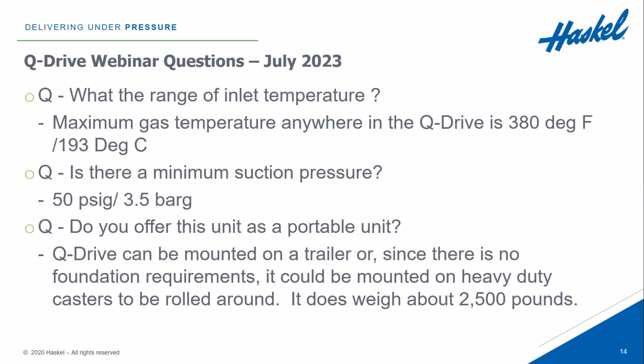So we probably can't handle that high an inlet temperature of the gas directly. We are working on an application right now where they do have very warm gas, so we are adding a pre-cooler to the inlet line so the gas will be cooled off before it goes in and gets compressed. So that's always an option we can add. Is there a minimum suction pressure? About 50 psi or 3.5 bar.